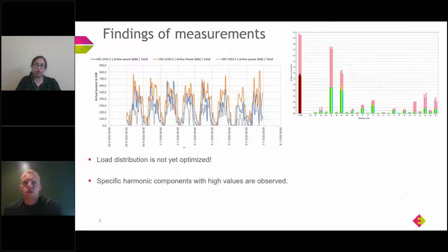Besides that, we also did harmonics measurement, as I showed you in the previous slide. As you can see in this figure, harmonics are increasing. Right now harmonics is not really a big concern because it is below the limit values, but the maximum value is close to 2.2% for the fifth harmonic, and the seventh harmonic is also close to 1.5%. So in the coming years, when more chargers are included in the installation, it can exceed the individual harmonic limits.